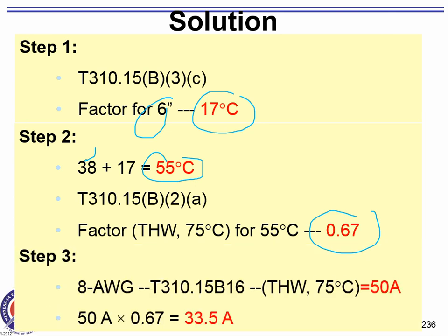And then, which column are you going to go to find the ampacity of 8 THW and why? Which column and why? Number 8. I needed an ampacity for number 8. Which column are you going to go to? 75. Why 75? Yeah, because we're derating. Once we derate, you go strictly by what the conductor is rated for.